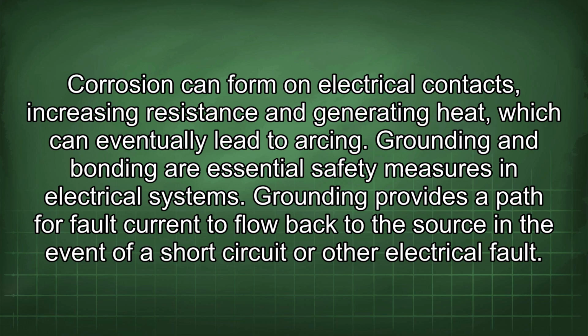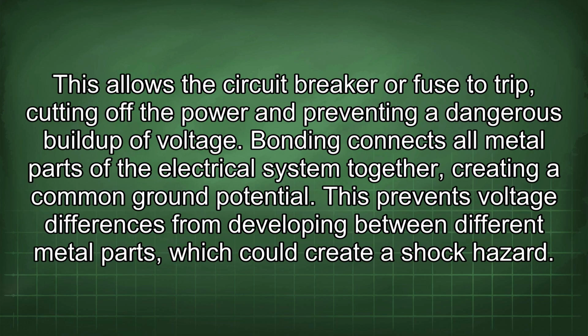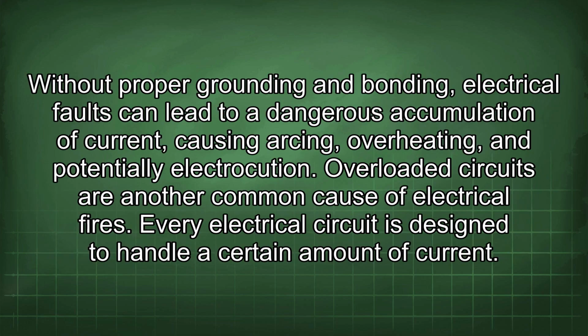Grounding and bonding are essential safety measures in electrical systems. Grounding provides a path for fault current to flow back to the source in the event of a short circuit or other electrical fault. This allows the circuit breaker or fuse to trip, cutting off the power and preventing a dangerous buildup of voltage. Bonding connects all metal parts of the electrical system together, creating a common ground potential. This prevents voltage differences from developing between different metal parts, which could create a shock hazard. Without proper grounding and bonding, electrical faults can lead to a dangerous accumulation of current, causing arcing, overheating, and potentially electrocution.